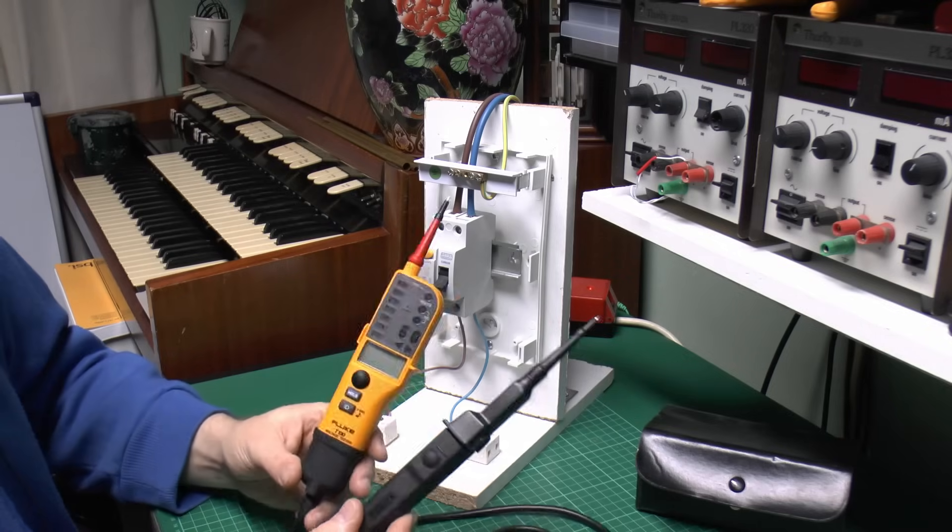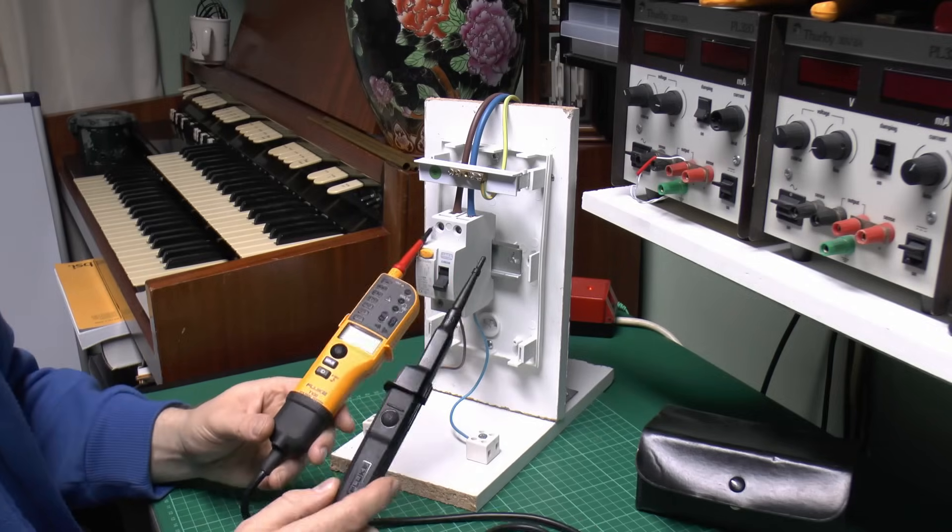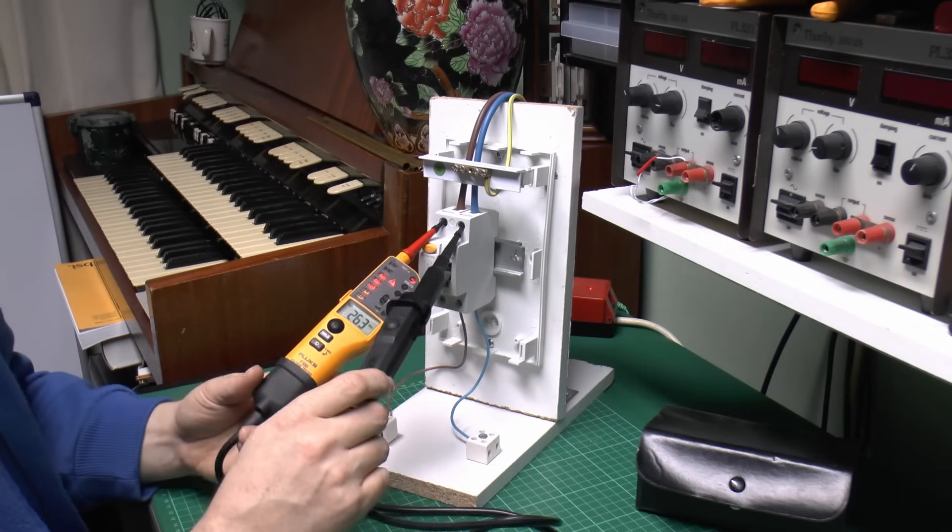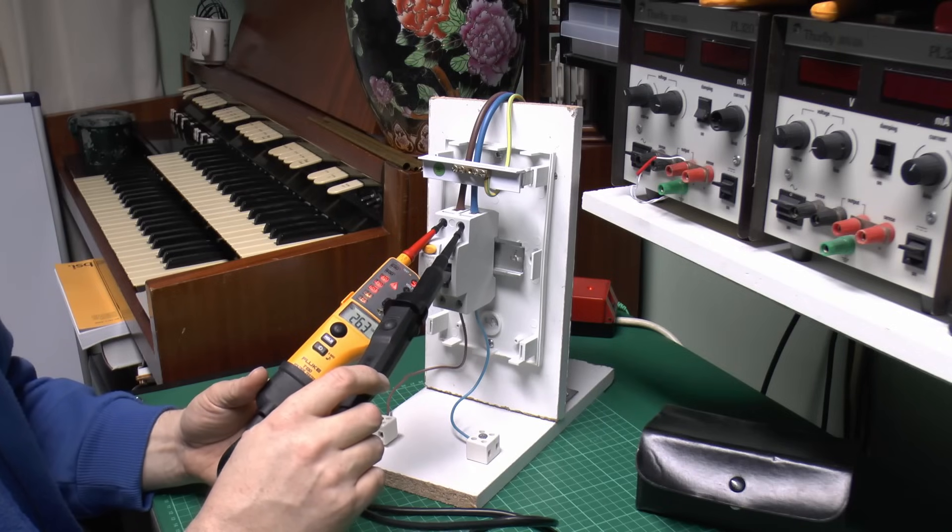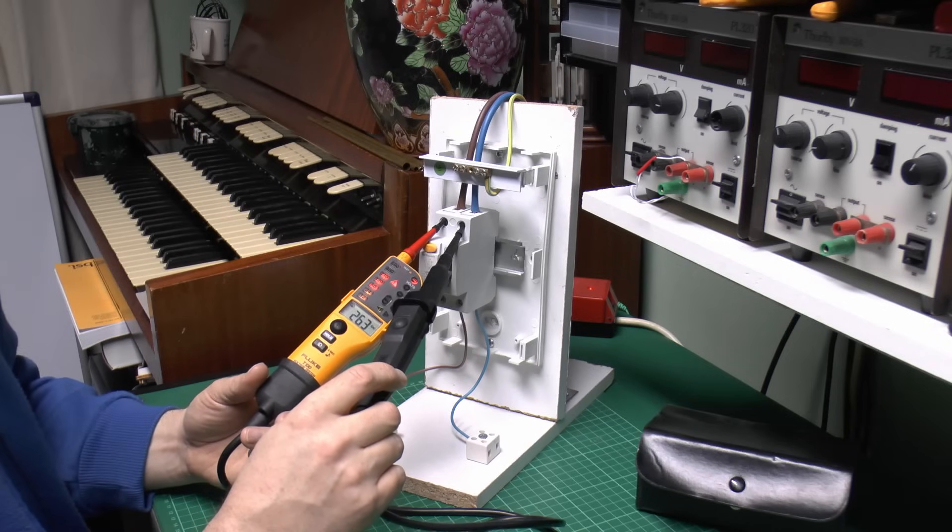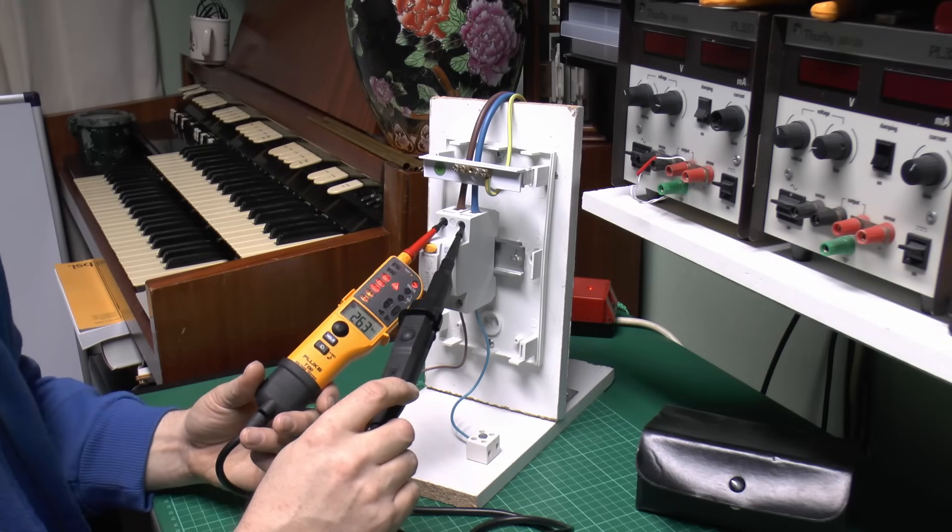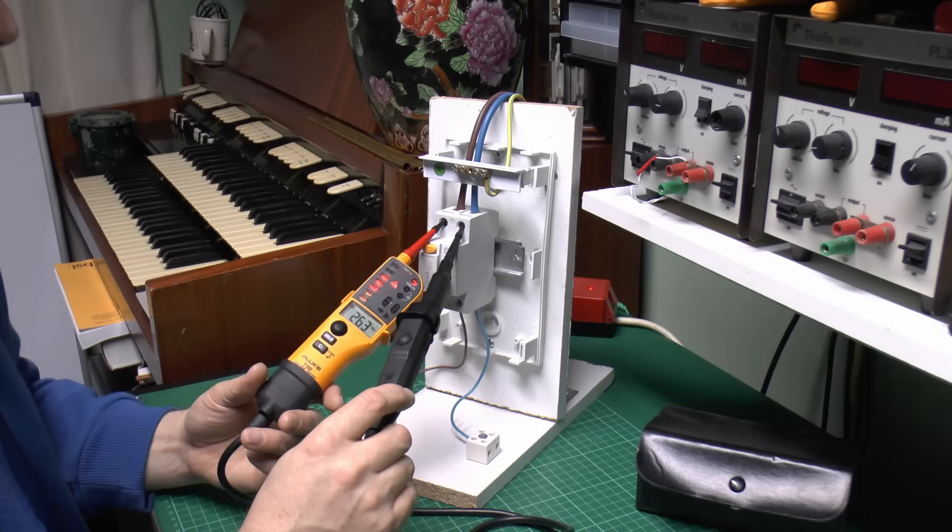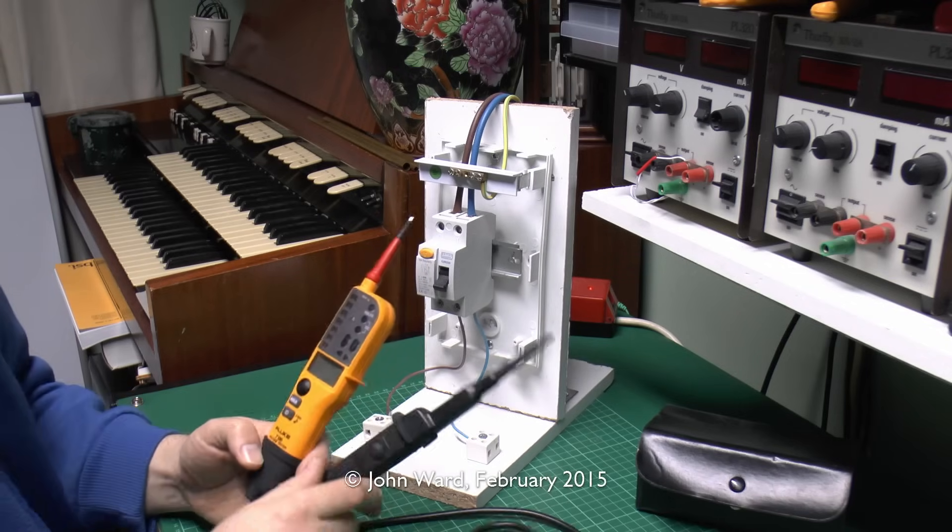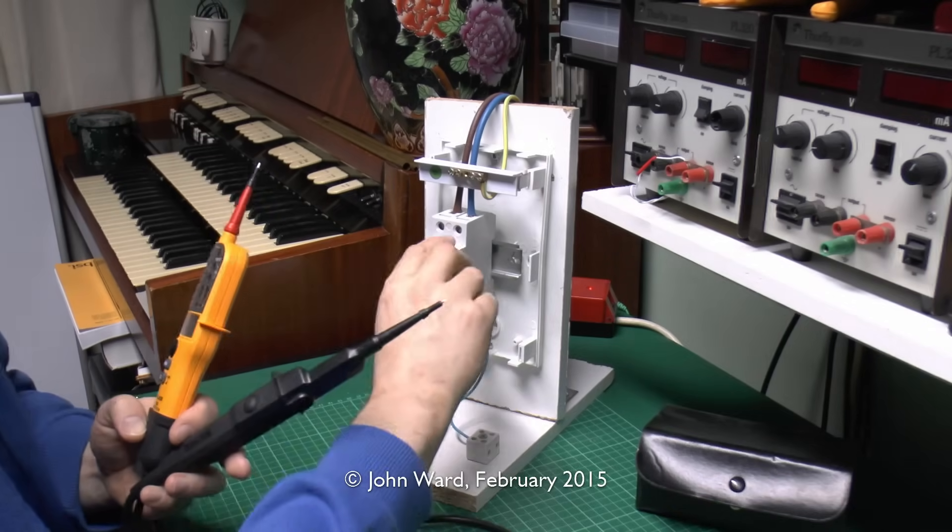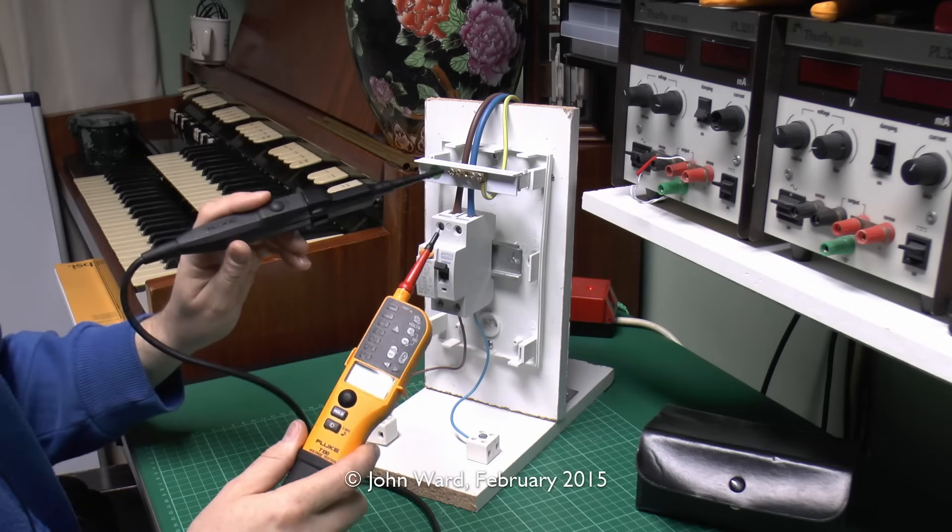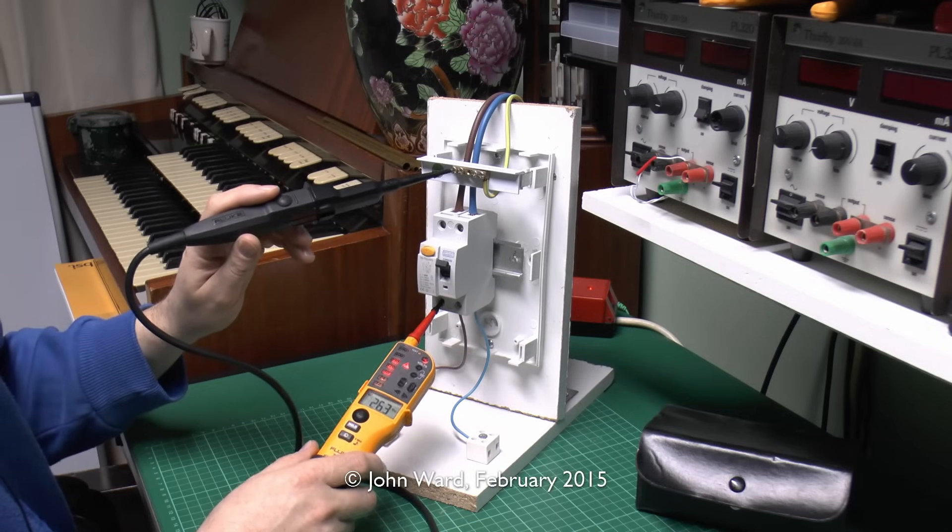Now for the rest of this demonstration I've turned off the beeper in this one because that's going to be really annoying, and of course in the real world you would leave that switched on. But again if you place the probes in here, you'll see that the LEDs along the top there will illuminate up to the 230 level. Again if the voltage was high it would have the 400 or the 690 illuminated, the little red triangle is illuminated, and the AC in the top right there has illuminated as well. And although it shows the voltage is 263, which of course is very handy, that's not the thing you're looking at to primarily detect whether the voltage is there or not, it is those red lamps above on the top section.